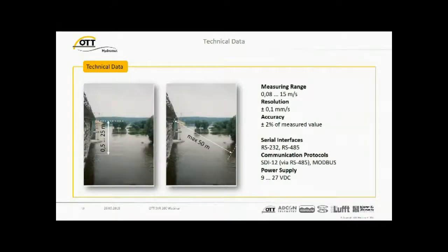We have a serial interface on board. That means we have an RS-232 interface and we have an RS-485 interface. And we can run 2 different communication protocols. We can send SDI commands via RS-485, and we can communicate via Modbus RTU. Power supply is a wide range between 9 and 27.